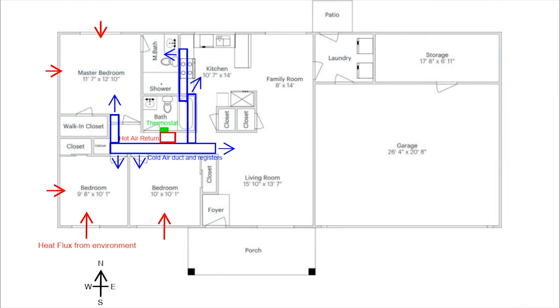So this gives two basic effects here. With the thermostat in the summer set at about 78, the master bedroom's usually around 82 Fahrenheit, and these bedrooms are somewhere between 82 and 85, which is not very comfortable. The other effect is if the AC or the heater is running and you hold one of the bedroom doors ajar and let it go, the AC will actually suck the door closed.